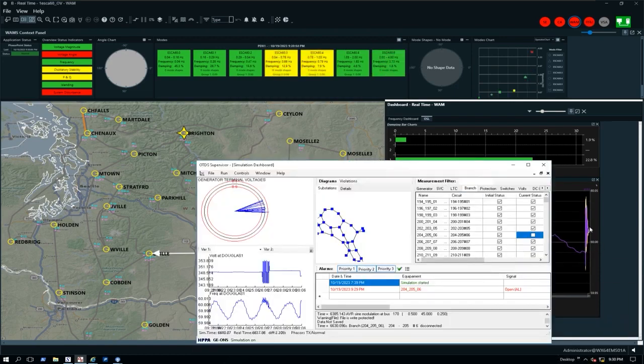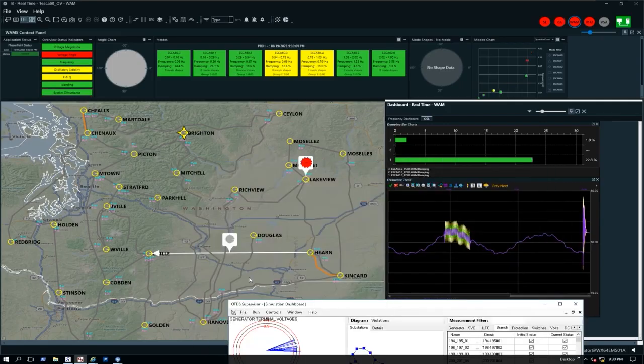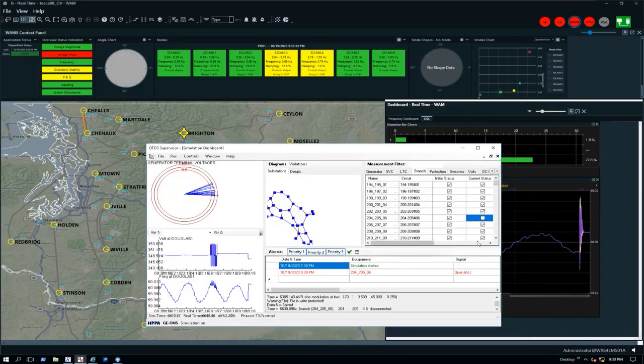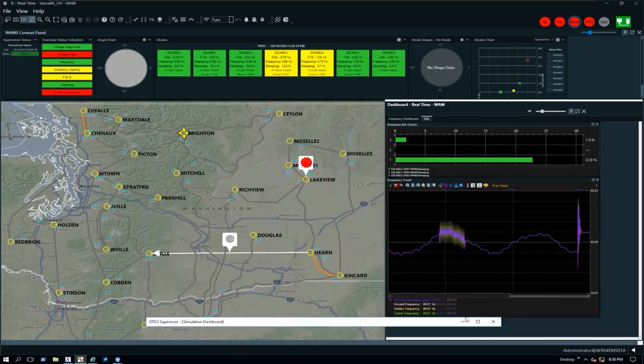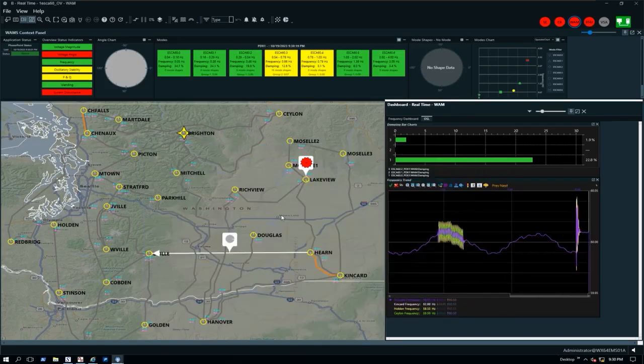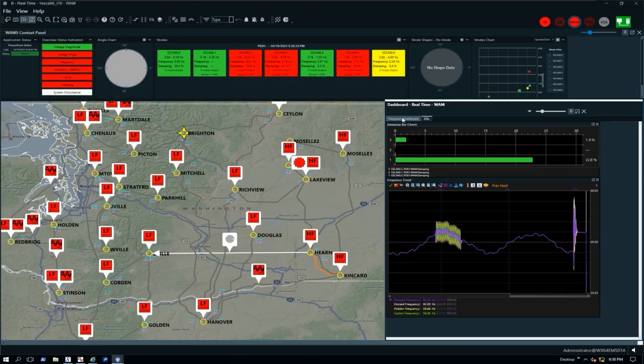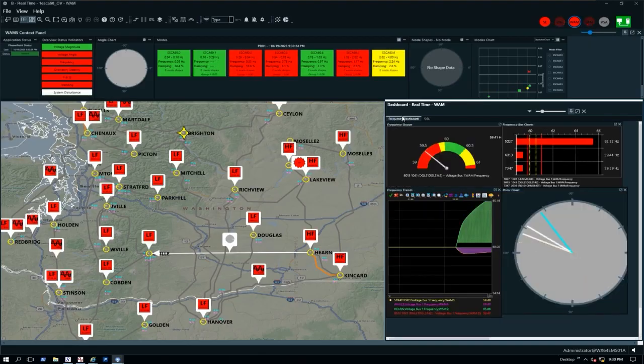And that transmission line has been taken out of service, so we get some voltage issues because we've weakened this system. We've got some frequency problems going on in that potential island. And then when the other transmission line is taken out of service, you'll see that we end up with a very large frequency excursion. So I'm going to change over to my other frequency dashboard.